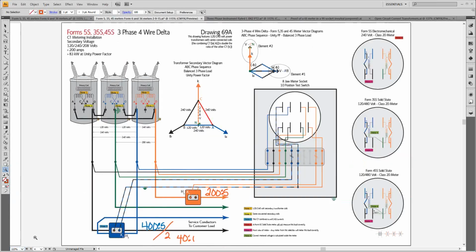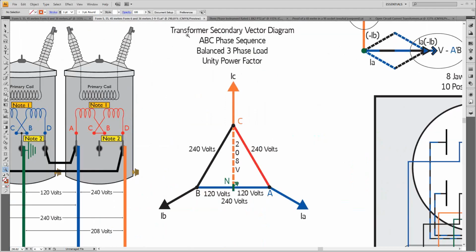So I'm going to zoom back out. In this setup, I've got three currents for my three-phase balanced load. That's what it says here. I'll zoom back in for a second. It describes the secondary vector diagram, ABC phase sequence, balanced three-phase load at unity power factor. At unity power factor, this is where my currents sit.